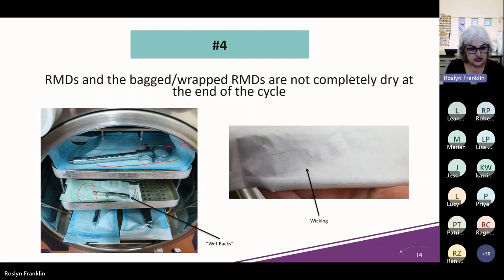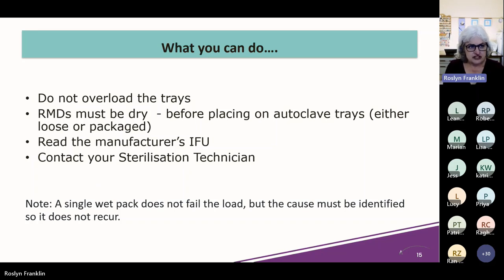What you don't want is wet packs at the end of the cycle. So let's say that's actually happened. Probably one of the main reasons I've found in my experience is because the trays have been overloaded. They've just piled too much on there, a couple on top, and it's just far too full and it cannot dry properly.